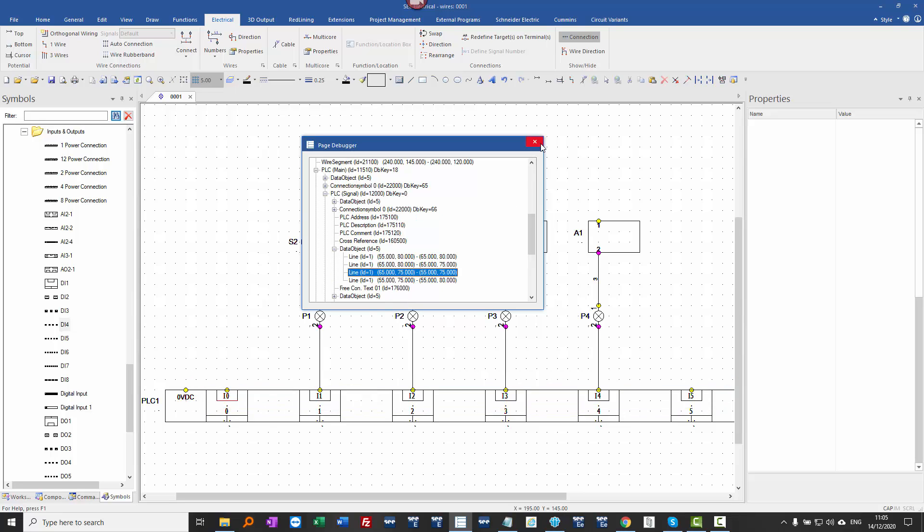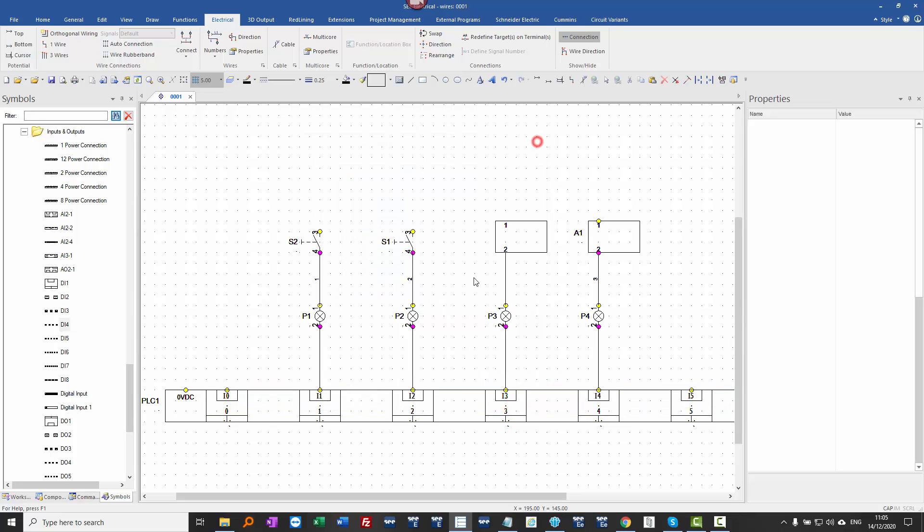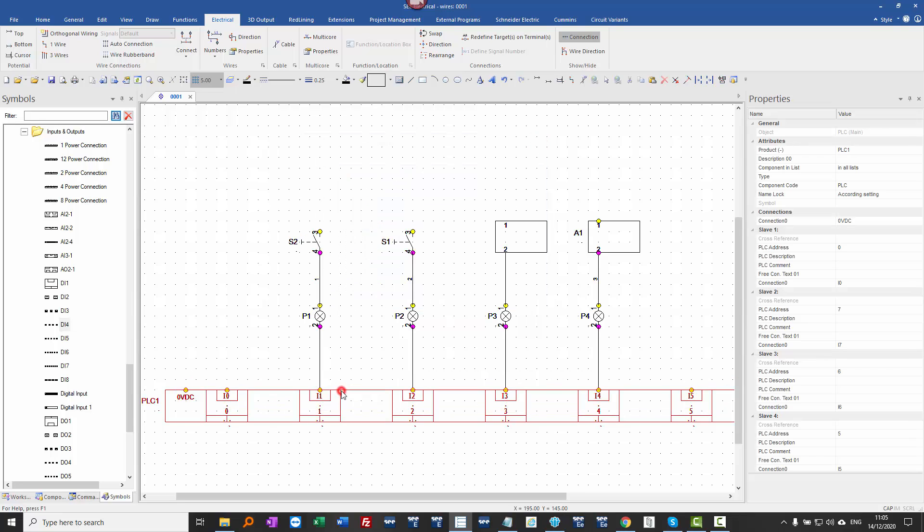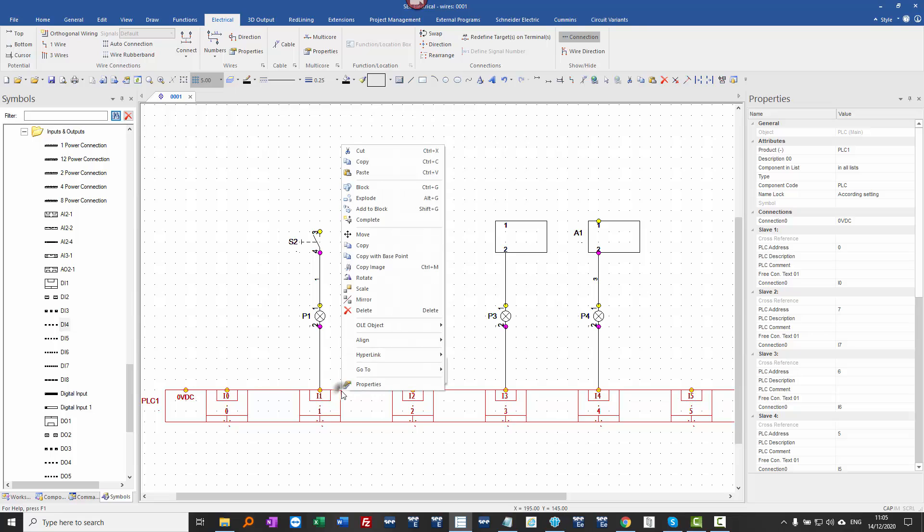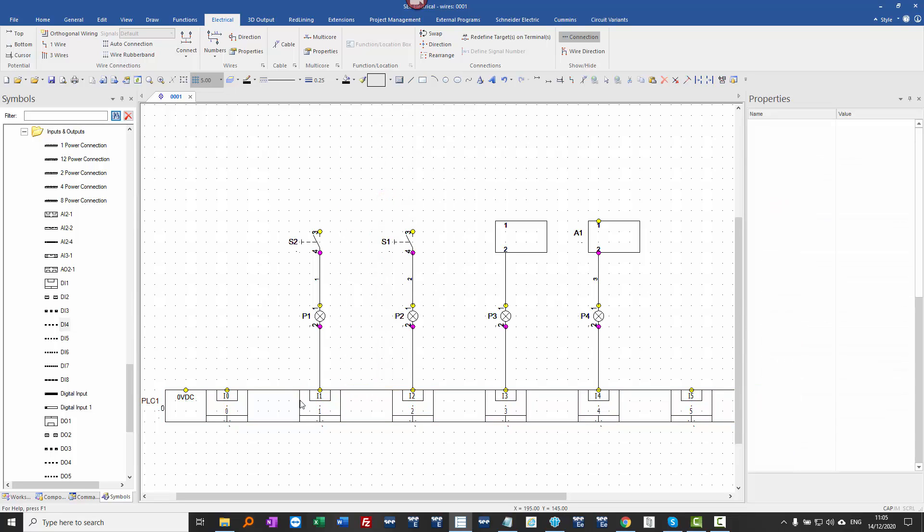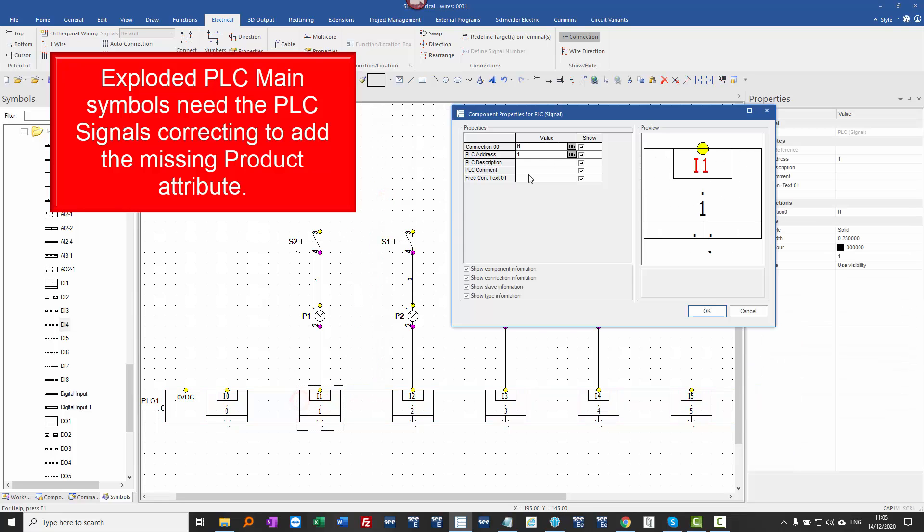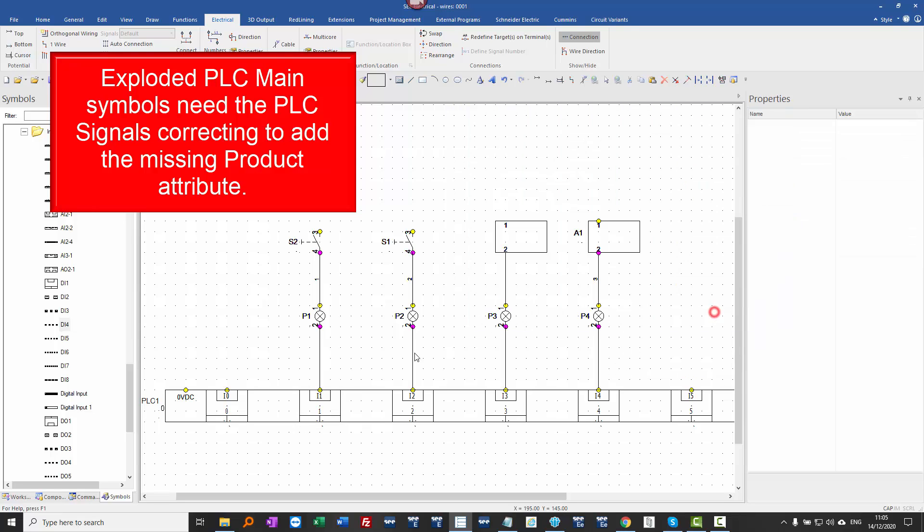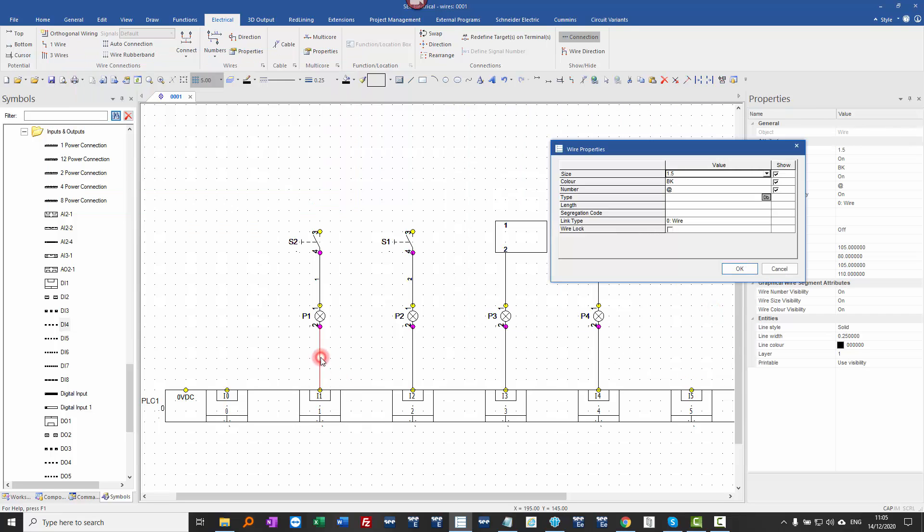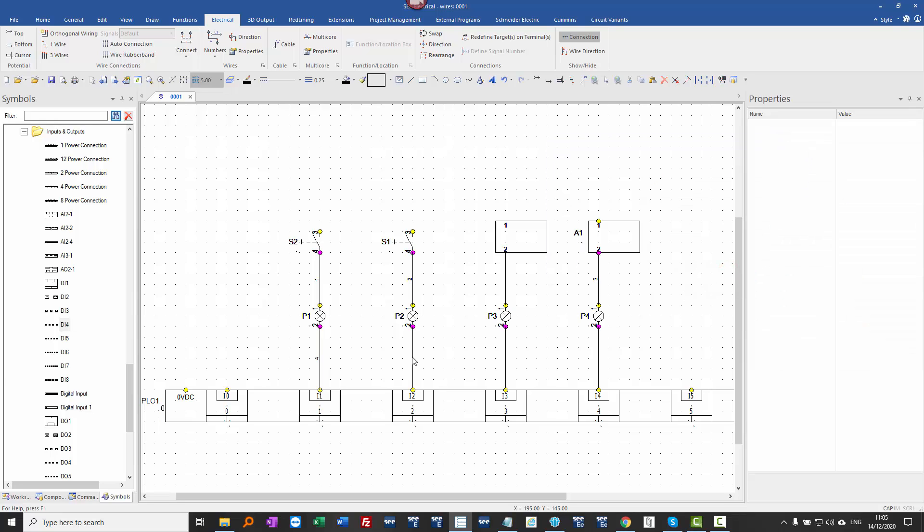The only way of working this is to right click and explode the symbol so that these are now separate PLC signal symbols. They don't have a component reference, a product, so they should really be corrected. But in this situation, I can now double click on this wire and assign a wire number. Before that, on any of these others, I can't assign wire numbers if it goes to a PLC signal within a PLC main symbol.